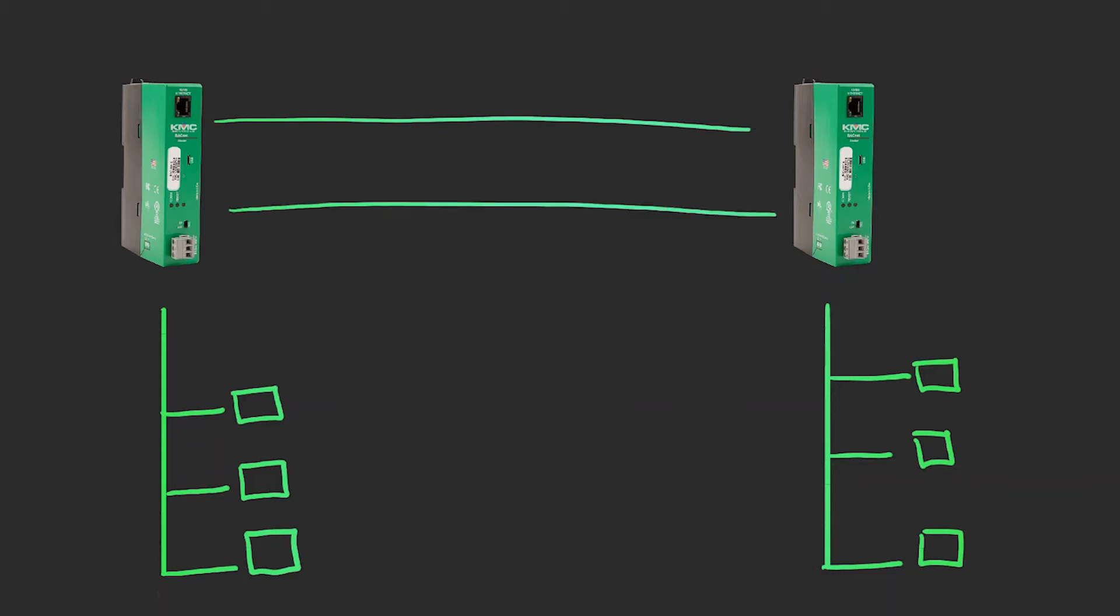A BBMD, or a BACnet broadcast management device, is a BACnet router that tunnels all broadcast messages it receives to all the other BBMDs and foreign devices it knows within your system.